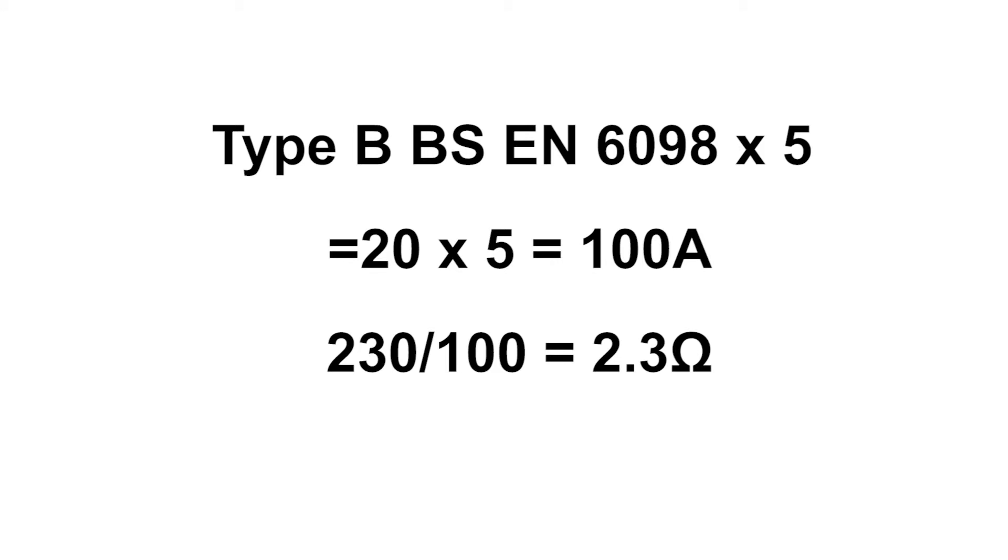We're using a 20 amp device. So if we multiply that by five, it means that when 100 amps flows through it, it must operate within 0.1 of a second. Clearly for 100 amps to flow, if I just use Ohm's law, 230 which is my voltage divided by 100 tells me that I've got a value of resistance of a maximum of 2.3.